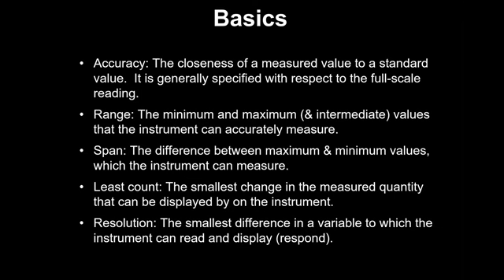Now, when you have such an instrument, we have to see the importance of the measurement. Suppose we are measuring surface heat loss for a furnace. Normally the furnace surface temperature is supposed to be about 60 or 65 degrees, depending on the furnace internal temperature. When it is 65 degrees plus minus 1.5 or plus minus 2 degrees, it is not going to impact your analysis to that level, because insulation losses are not expected to be more than 5% or 6% of the total losses. So a reading of plus minus 1.5 degrees probably will not make that much of a difference, because the criticality is different and the values and range are different. Accordingly, we have to select the range and application of the instrument.